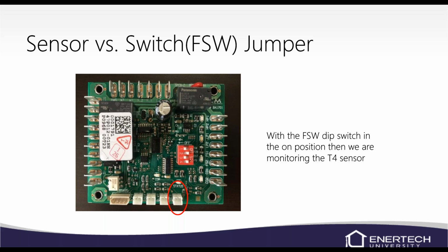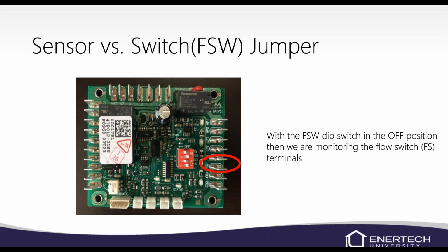Now, if you want to put this board on an older unit that has a flow switch and you want the sensors, we can send you the sensors and this board, and we can tell you where we want those sensors put, and we can do that. But if you don't want to go through that trouble, then the board that you will get will be this board, and you'll have to flip that dip switch to monitor the flow switch and not the T4 sensor. So again, with the dip switch in the off position, now we're monitoring those terminal connections. So we're looking at a paddle switch that's in the water line right near the source heat exchanger.